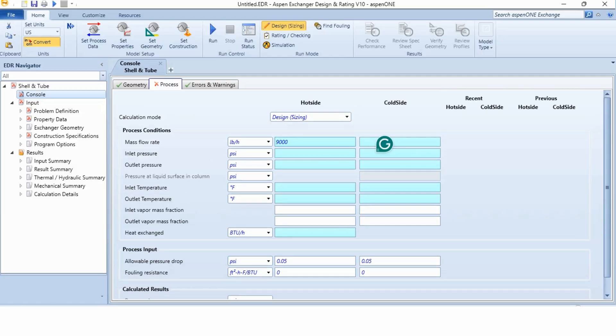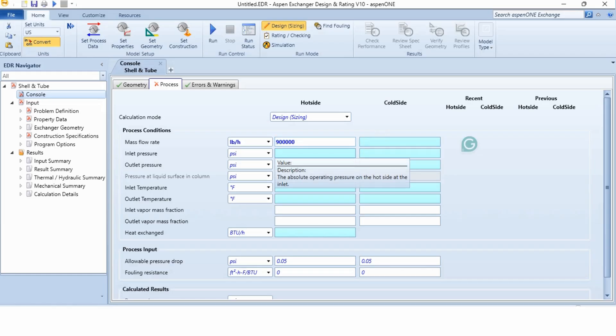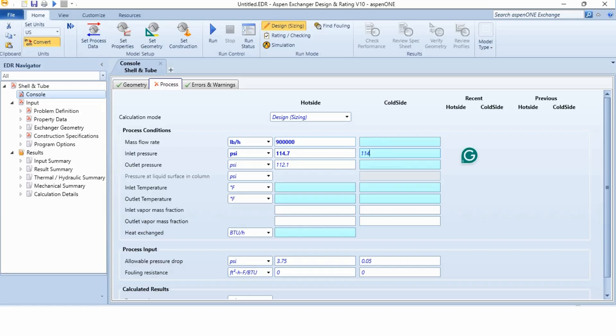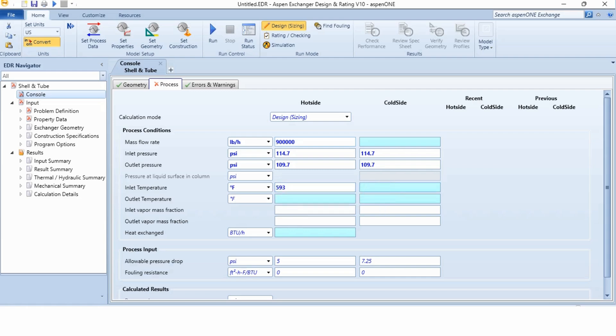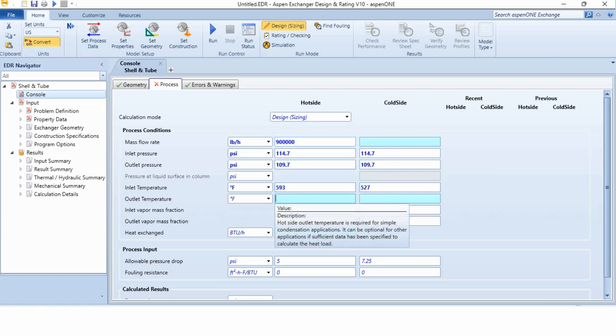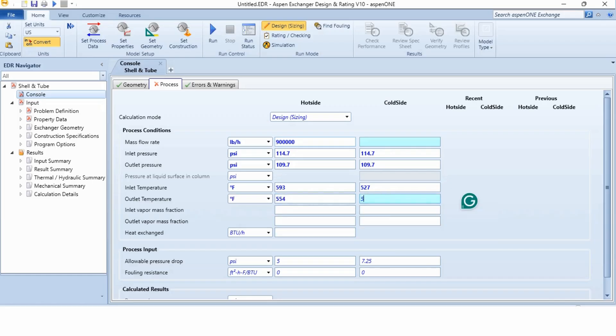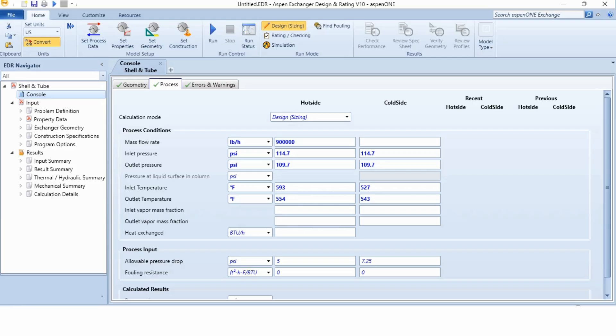So first thing is to specify the flow rate. So that is specified over here. Then the inlet pressure is 114.7 for both streams and the outlet pressure is 109.7 for both streams as it has been given to us in the problem statement. The inlet temperature of the hot side is 593 degree Fahrenheit while that of the cold stream is 527 degree Fahrenheit. And outlet temperature of the hot stream is 554 degree Fahrenheit and cold side is 543 degree Fahrenheit.